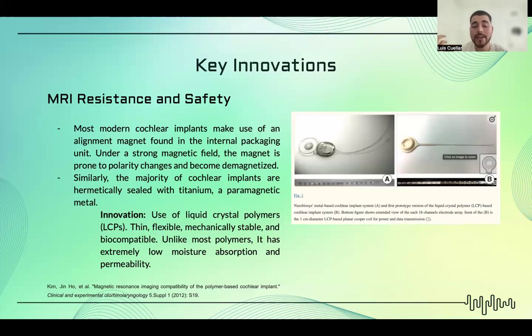The titanium package causes an image artifact, so it distorts the image that the MRI can produce due to the fact that it's a paramagnetic metal. Since it distorts that image, it prevents people using cochlear implants from getting clear results of what they need. Whenever they need to go to the doctor and get an MRI, you don't want to have less of a chance of detecting maybe a tumor or anything like that, just because of the image artifact that the titanium package creates.